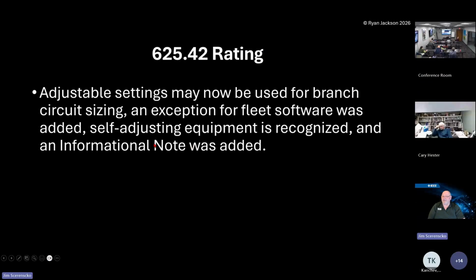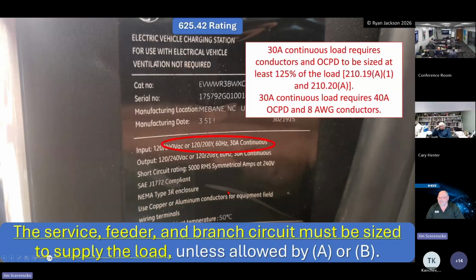The other thing that's been happening is if you have an adjustable setting, it may now be used for the branch circuit sizing. An exception for fleet software was added, self-adjusting equipment recognized, and an informational note was added. So a lot of this comes up at these conferences: it says I can adjust it down to 48 amps or something like that, right? And I can put this at 125%. I can use the 40 amp breaker, 40 amp conductors, blah, blah, blah.